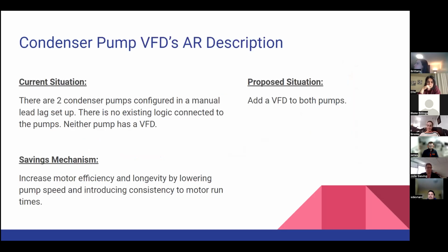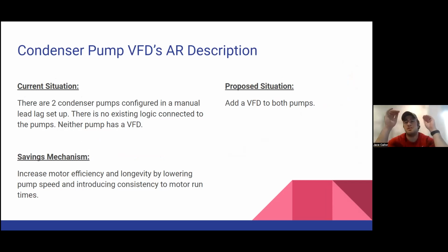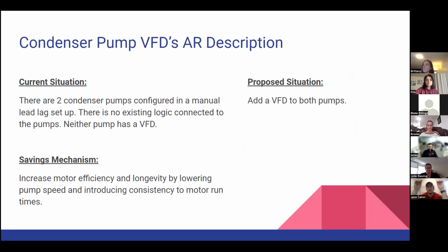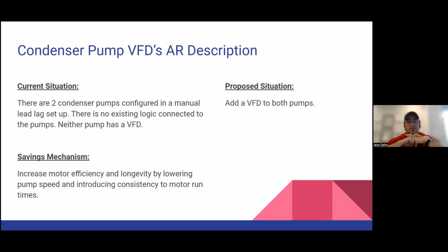Awesome. Thank you, Brooke. Well, so the condenser pump VFD AR, the current situation: there are two pumps. There are two condenser pumps that are in a lead lag setup, but there's no logic between the two. So it's kind of a manual lead lag system, and neither pump has a VFD. So what we're proposing is that we want to add a VFD to both pumps, because VFDs increase the efficiency and the longevity of the motors, and ultimately just introduce consistency that can save money, so that the pump's not just jumping from 0 to 100, but can save money by being consistent.